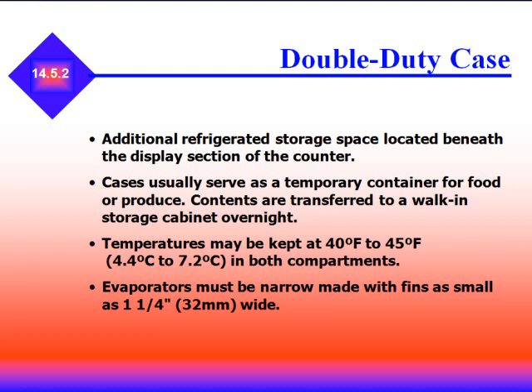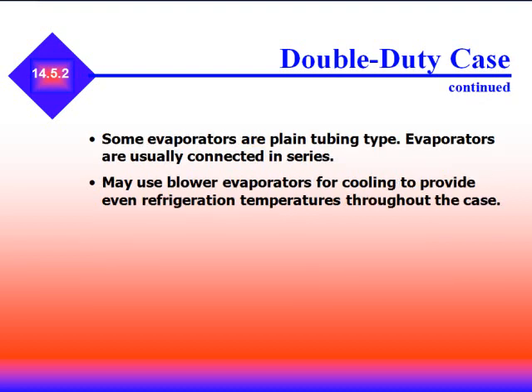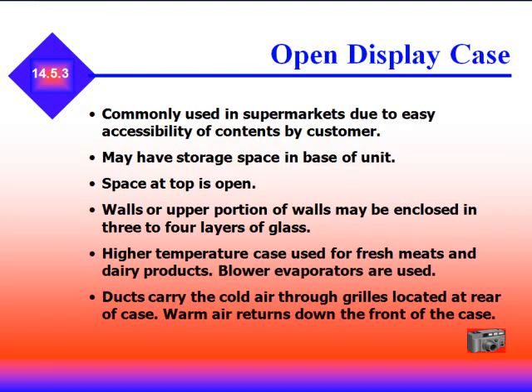A double-duty case includes additional refrigerated storage space beneath the display section. Cases usually serve as a temporary container for food; contents are transferred to a walk-in cabinet overnight. Temperatures may be kept at 40 to 45°F in both compartments. Evaporators must be narrow, made with fins as small as 1¼ inches wide. Some evaporators are plain tube types and are usually connected in series in double-duty cases. They may use blower evaporators for even refrigerant temperature throughout the case. Open display cases are commonly used in supermarkets due to easy accessibility; they may have storage space in the base and walls or upper portions enclosed in three to four layers of glass. High-temperature cases are used for fresh meats and dairy products, using blower evaporators with ducts carrying cold air through grills at the rear and warm air returning down the front.